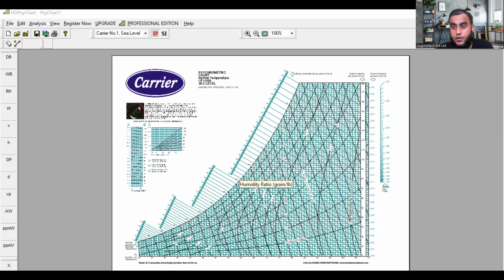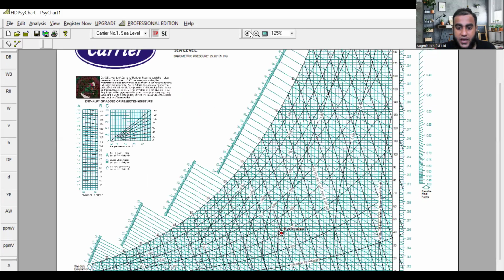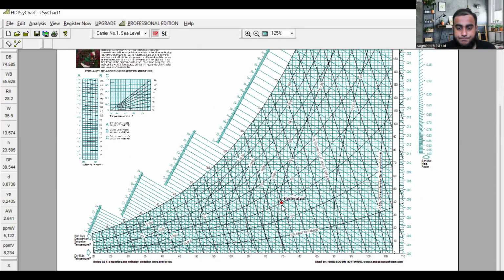But see, in which unit is this 38.7? Grains per pound. But in this formula, the humidity ratio value which we have to enter is not in grains per pound. Okay, I will show you. So whatever you have selected, just keep it, and finally you have to hit apply. When you hit apply, here you will get the psychrometric software. Can you see this software? All of you let me know, please. And you will get the exact location.